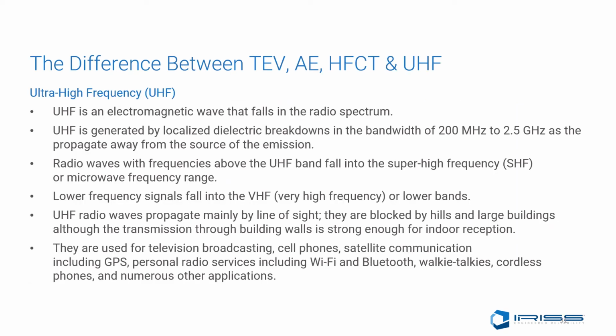The difference between UHF versus TEV, AE, and HFCT. UHF stands for ultra high frequency. UHF is an electromagnetic wave that falls in the radio spectrum. UHF is generated by localized dielectric breakdowns in a bandwidth of 200 MHz to 2.5 GHz as they propagate away from the source of the emission.